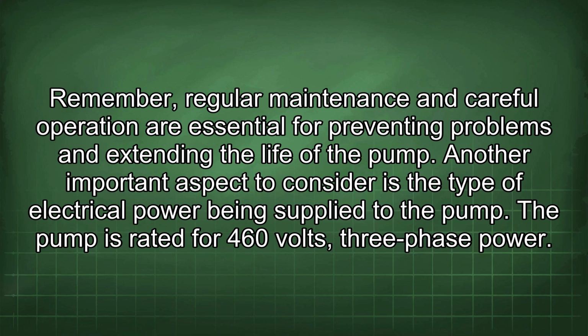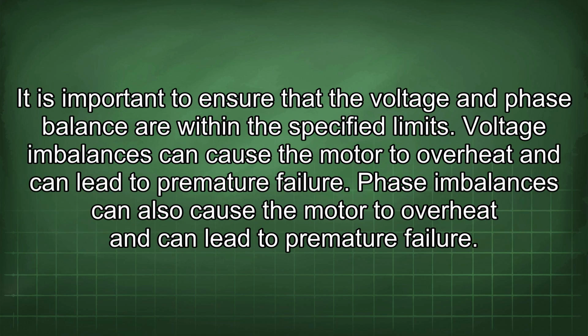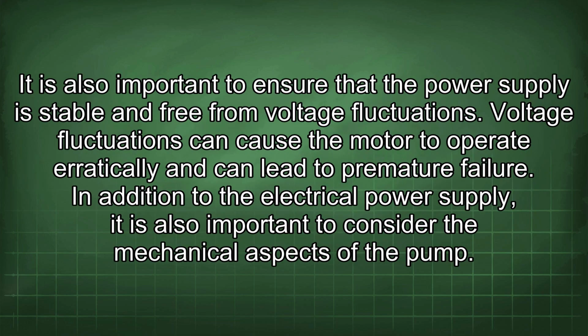Another important aspect to consider is the type of electrical power being supplied to the pump. The pump is rated for 460 volts, 3-phase power. It is important to ensure that the voltage and phase balance are within the specified limits. Voltage imbalances can cause the motor to overheat and can lead to premature failure. Phase imbalances can also cause the motor to overheat and can lead to premature failure. It is also important to ensure that the power supply is stable and free from voltage fluctuations. Voltage fluctuations can cause the motor to operate erratically and can lead to premature failure.